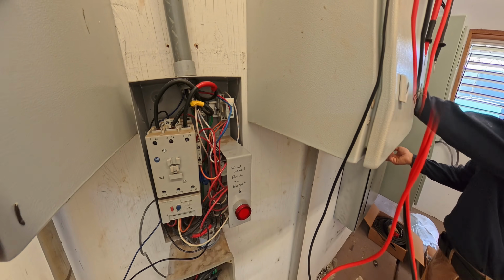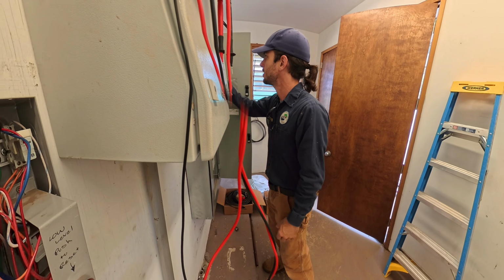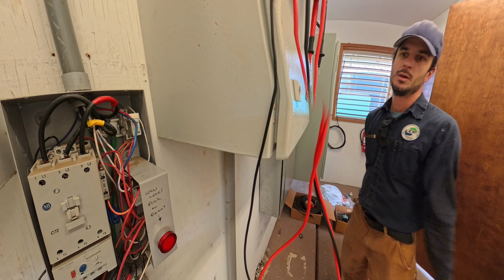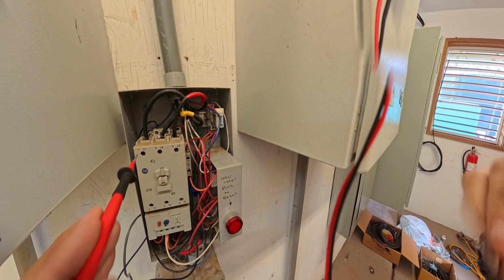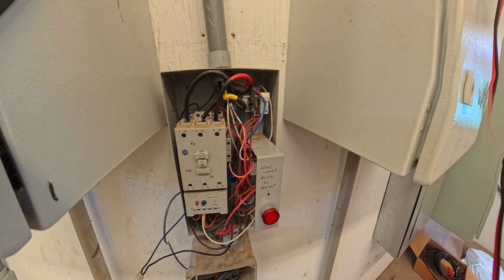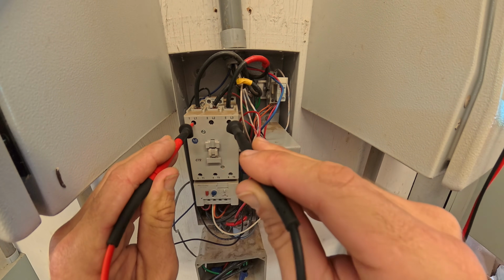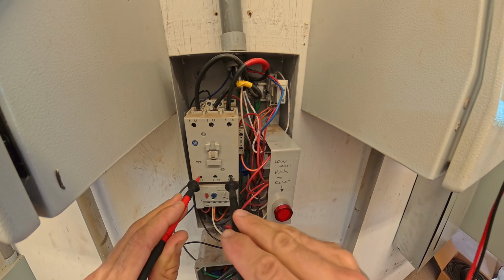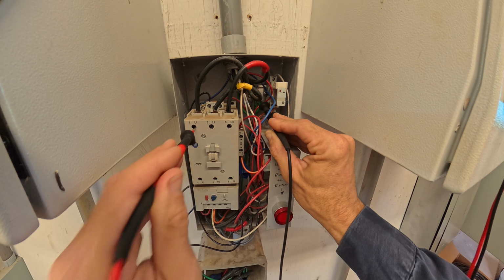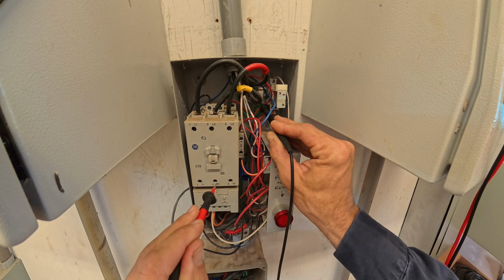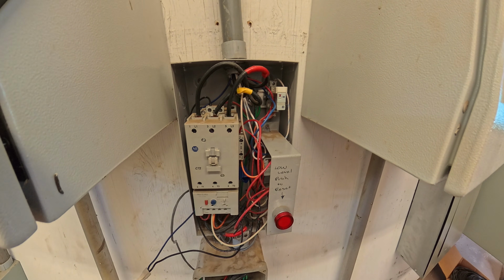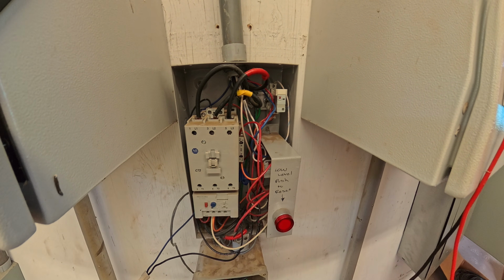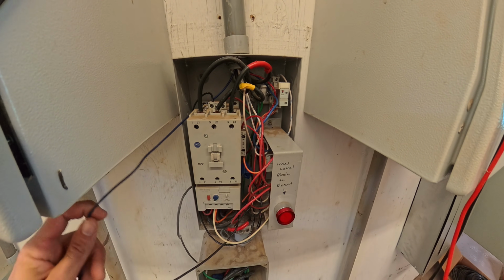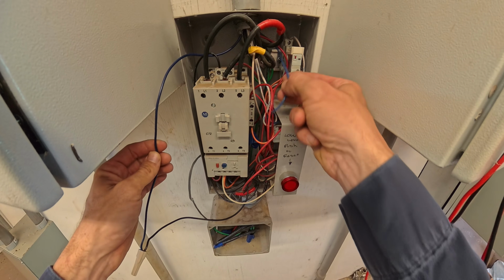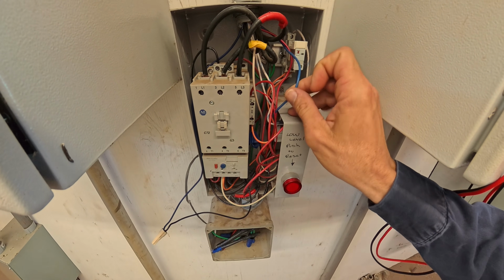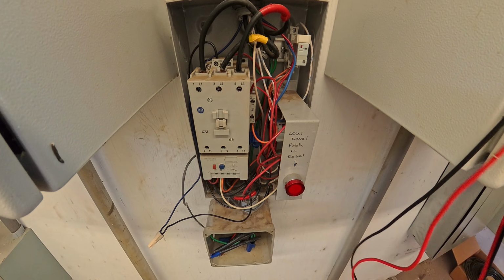Let's shut off our pump power as well. So we're getting all friendly in there. So now we shouldn't have any 480 in here. Let's check that. Good. Good. Ground. Good. Okay, but there is, I suspect, still some 120 in here, and I want to just identify where it is before I turn it off. So here's our return back from our controls, and here is our source out. It's going on to that little relay in the back there, and yeah, he's lit up.